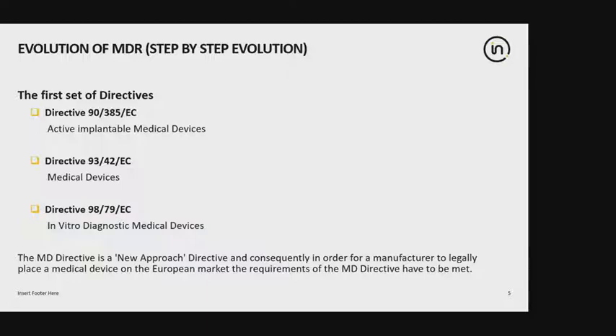Now, the medical device directive was a new approach directive, and consequently, to legally place a medical device in the European market, the requirements of the medical device directive have to be met. The directive was brought in so that the manufacturer essentially has to meet only these requirements to place the medical device into the European market, and does not have to follow any other legislation of the individual countries. All 27 countries adopted these directives into their national laws, and only one set of law was applicable to the medical device, which was 93/42 or 90/385.